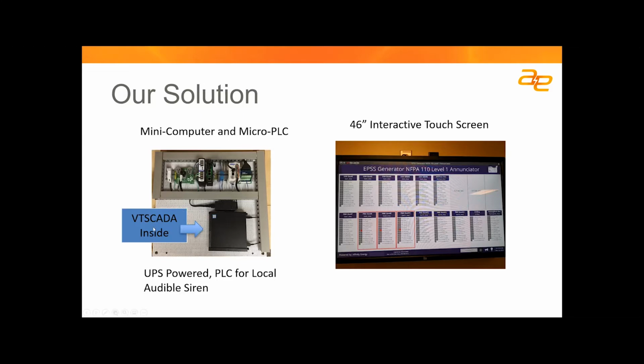We also leave a little open space here. Typically we try to get these control panels off a UPS circuit, because it's important that both this display and the panel itself be under uninterruptible power, so those are usually on a UPS circuit within the hospital.